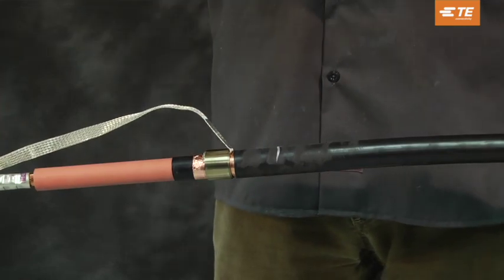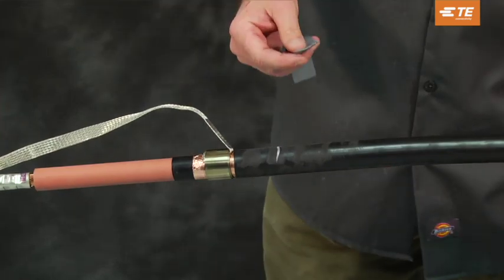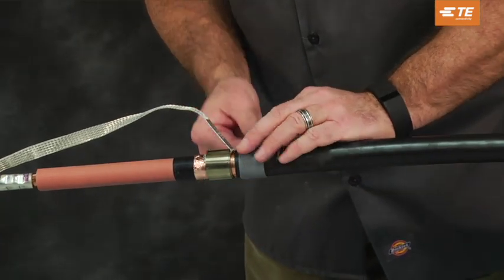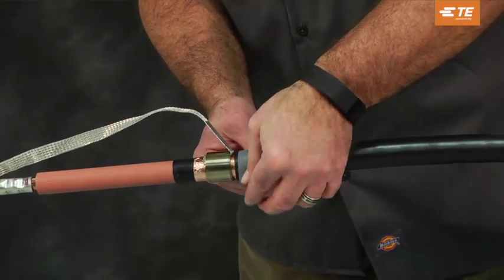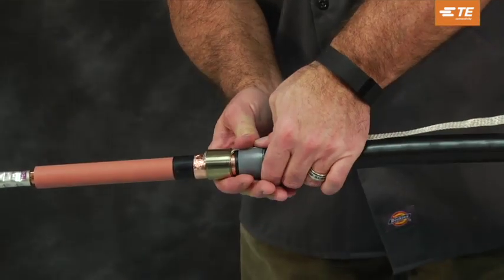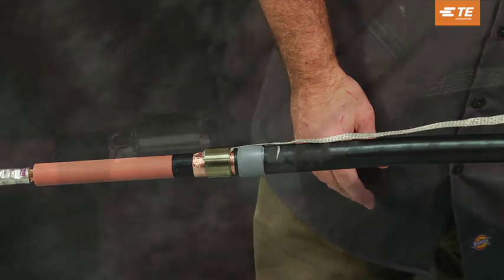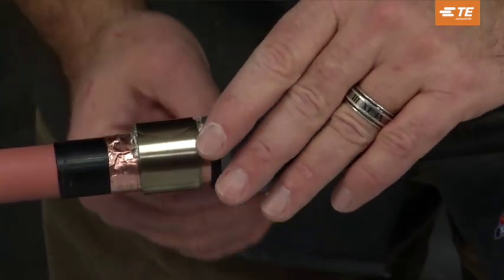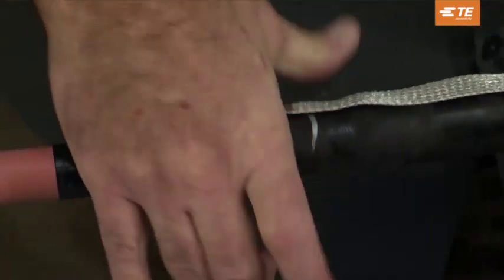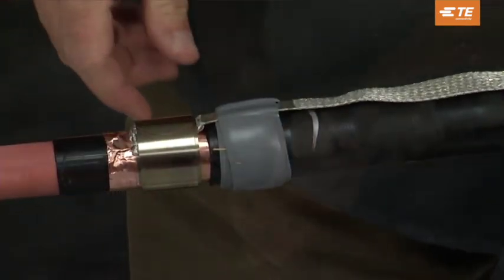Tighten the clamp by twisting it in the direction it is wrapped. Lift the ground braid away from the jacket. Using light tension, wrap one layer of gray sealing mastic onto the cable jacket as shown. Lay the braid back over the jacket and press the moisture-blocked section of the braid into the mastic.